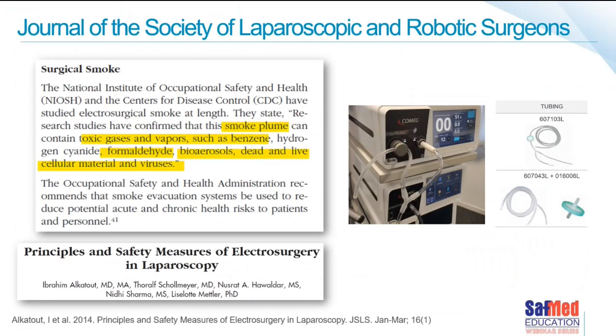We often use diathermy, electrocautery, of course, the correct terminology, during laparoscopic surgery. The surgical plume that's created can cause all sorts of issues. Firstly, it can fog our vision, so we can't see what's going on. And over and above that, it can raise the intra-abdominal pressure for the patient, again putting the patient at risk, as we had said. Some insufflators might have the capacity to automatically exhaust some of the gas, which is, again, a very nice feature to have. But when you have that feature, what you don't want is the gas going back into the insufflator itself and contaminating it. So it makes sense if that surgical plume's gas is exhausted into the atmosphere instead of into the insufflator itself.